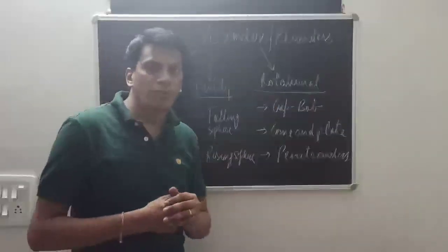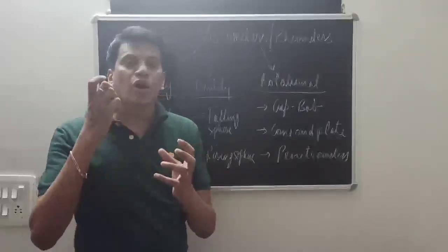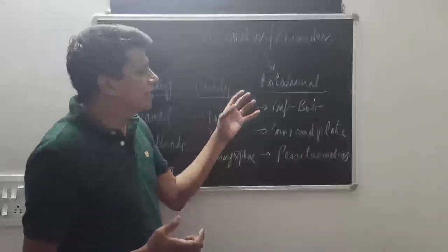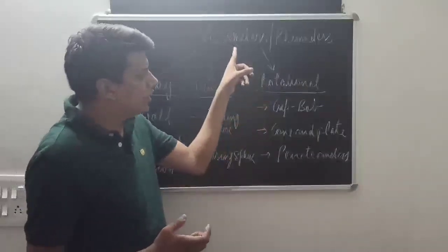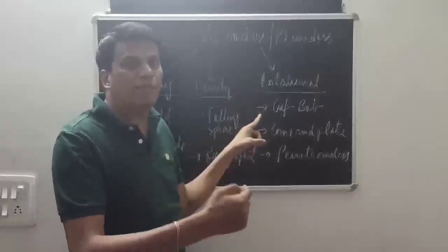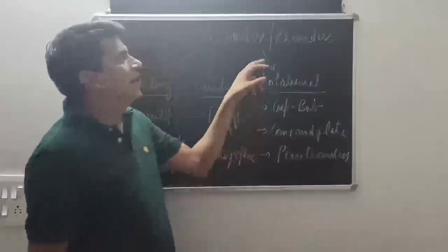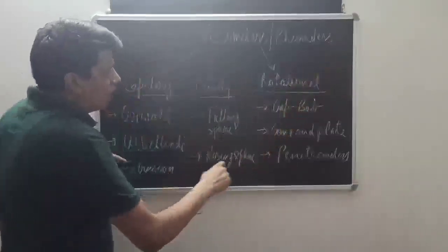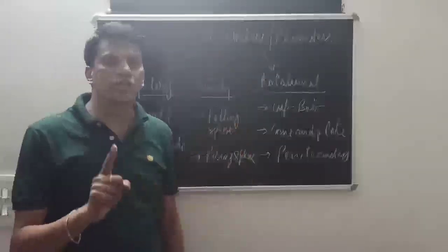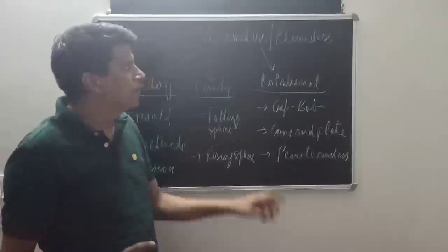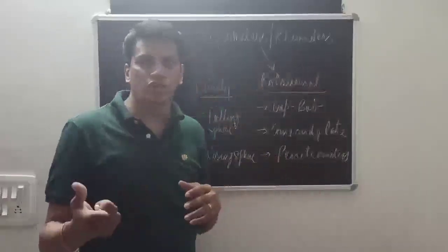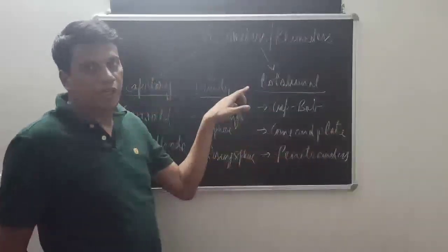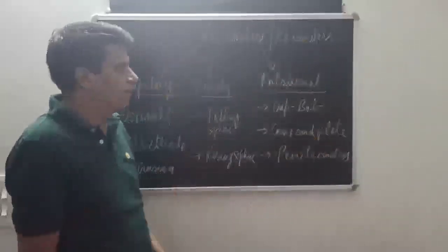Then third is rotational viscometers, where some part is moving and because of that movement shear or stress values are there, and therefore we are measuring the viscosity of the material at different points of shear or stress, and therefore these are called rheometers. Traditionally all of them are called viscometers because they measure viscosity at only one point. Since this is measuring rheology, viscosity at different shear values, they are called rheometers. But generally rheometers is used for all of them.